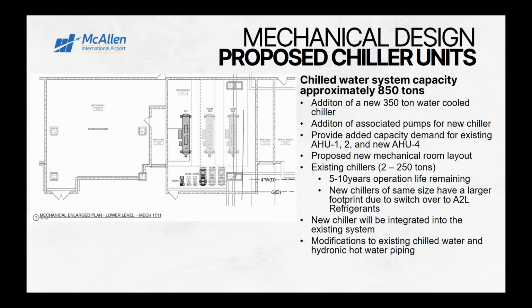The 2025 ASHRAE industry updates now don't allow chillers with the refrigerant we currently have, 134A. The 454B is the new standard. So when we get to construction, the chillers will need to be replaced. The existing chillers, put in about 2012, are also close to the end of their useful life, so we'll look at how we implement and replace the existing chillers in the building.